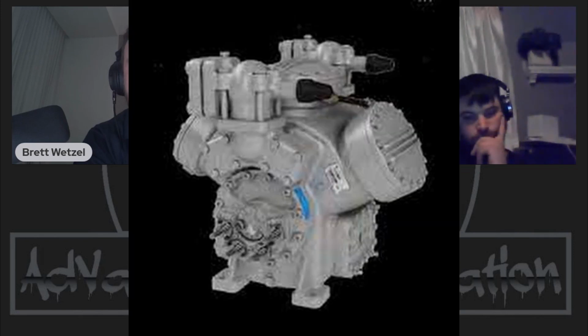And so one of the ideas about this ammonia over CO2 was that I wanted an all-natural system that was very much like the systems we already had installed, so the service technicians didn't really need to learn a whole new trade to do this. So this system that I'm going to describe later on is really our two-stage direct drive system. And instead of the pipes going out to the evaporators, they go to two liquid feed systems, a low temp and a medium temp. And the compressors, I got Carlyle to build us an ammonia version of the 5-line. The motors are the same. The control panels are the same. The oil equalizing is the same.